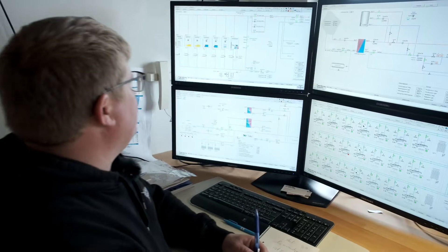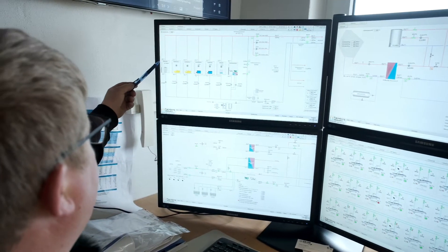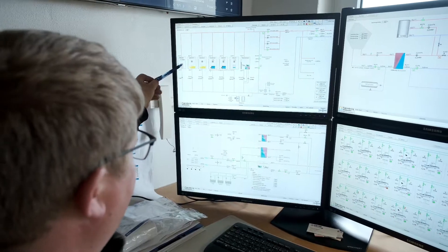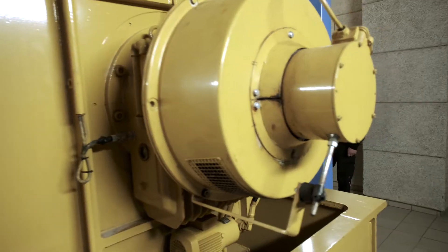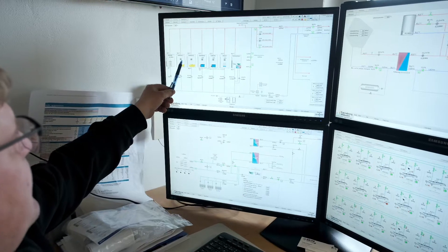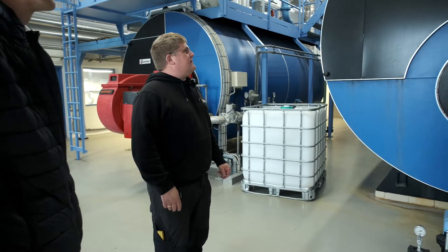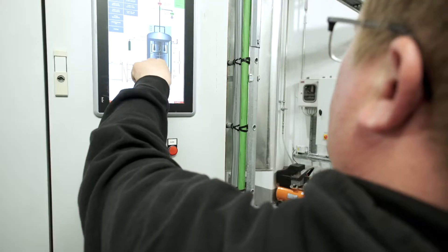This is our engine control room where we manage our assets. You can see our accumulation tank where we can store approximately 125 megawatt hours of heat. We have our CHP plant, approximately 7.6 megawatts of electrical power, our backup natural gas boilers, 10 megawatts and 4 megawatts, our electrical boiler, 10 megawatts, and our heat pump.